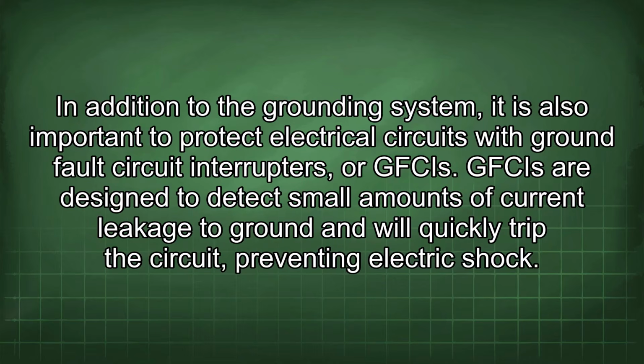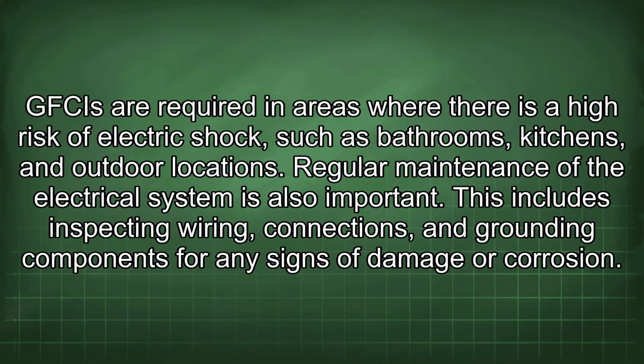In addition to the grounding system, it is also important to protect electrical circuits with ground fault circuit interrupters, or GFCIs. GFCIs are designed to detect small amounts of current leakage to ground and will quickly trip the circuit, preventing electric shock. GFCIs are required in areas where there is a high risk of electric shock, such as bathrooms, kitchens, and outdoor locations. Regular maintenance of the electrical system is also important.